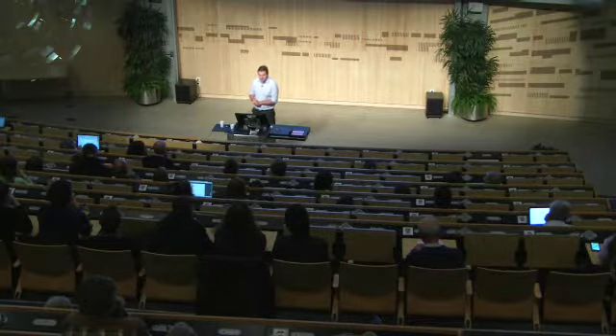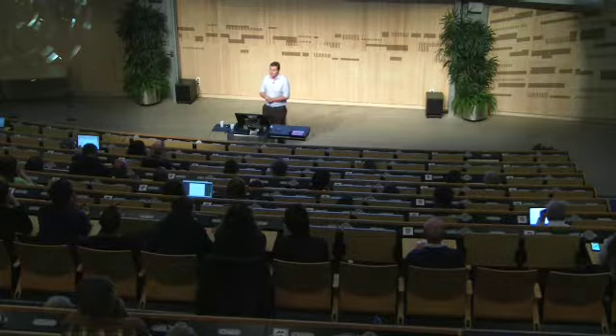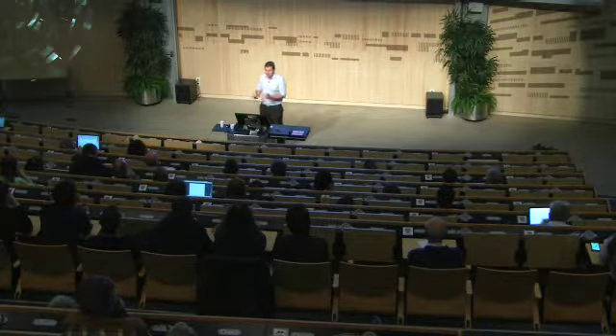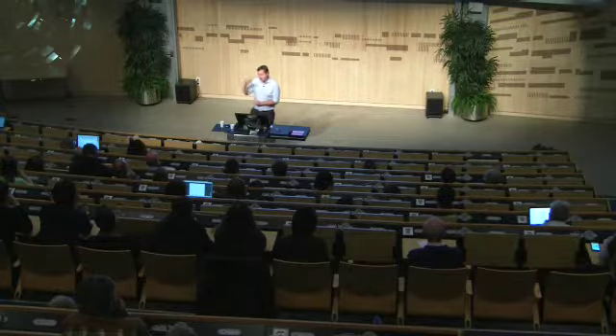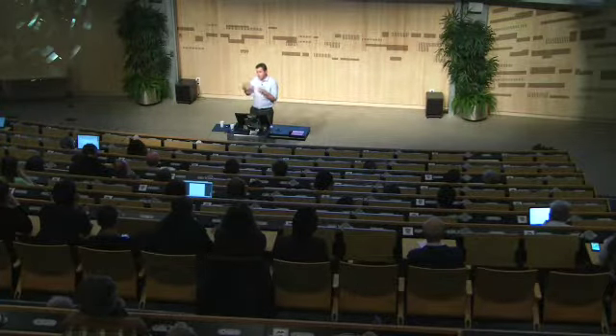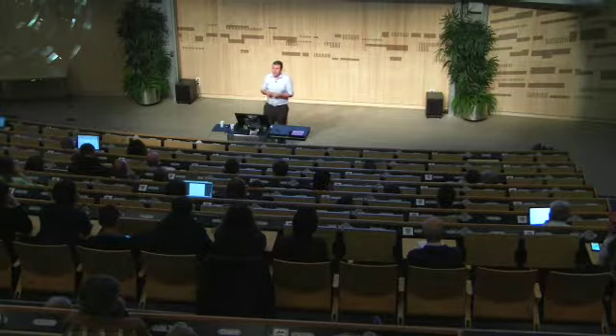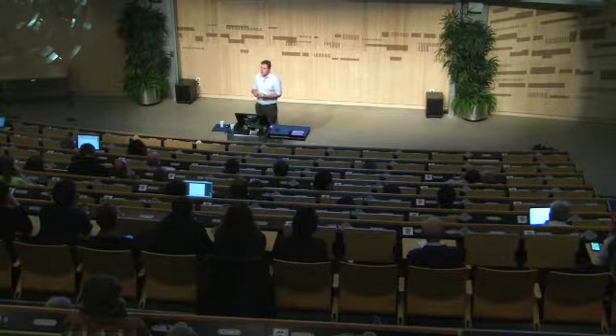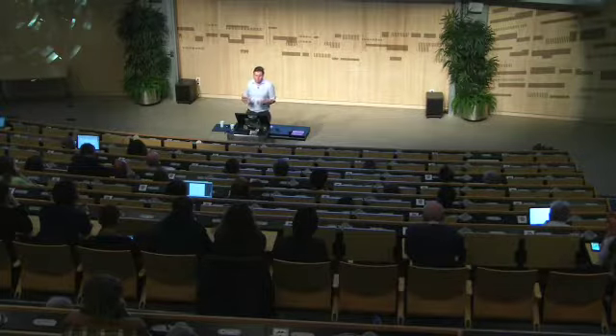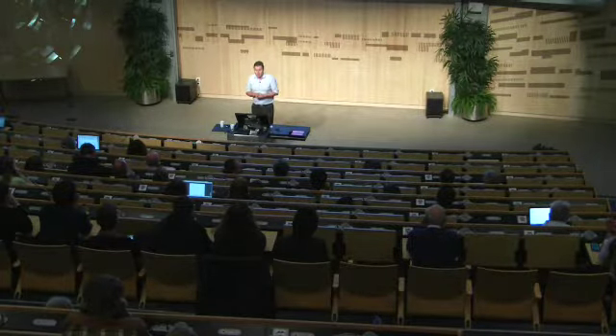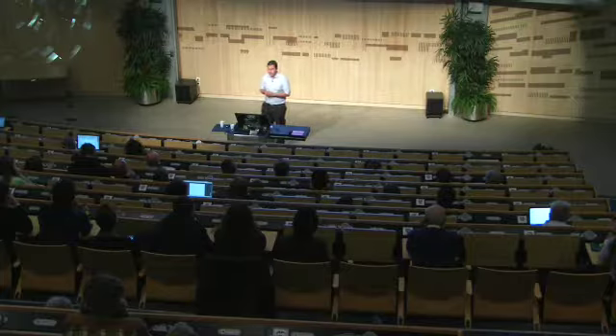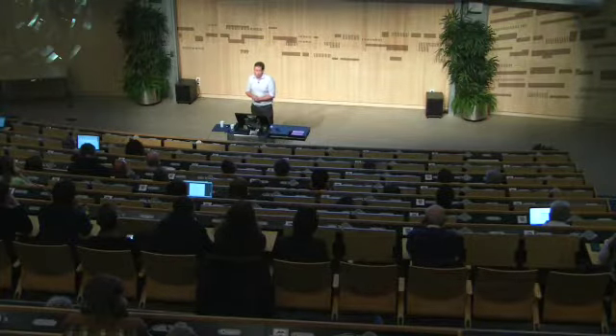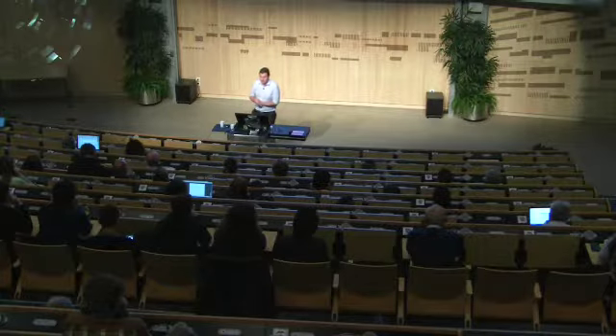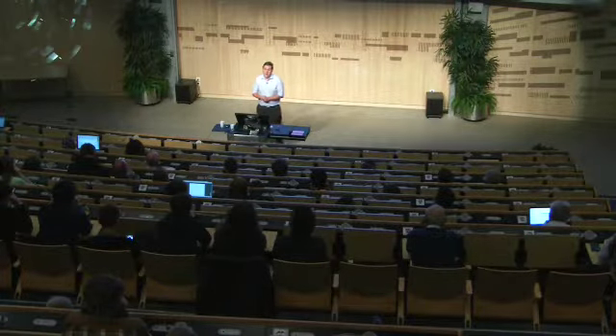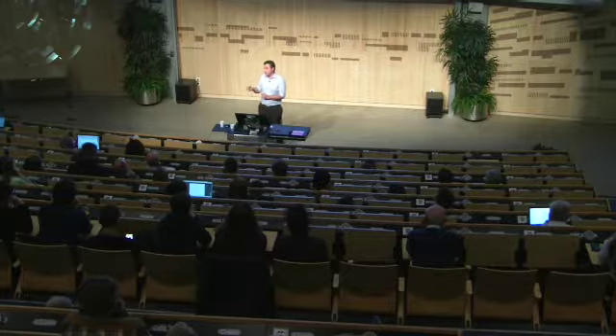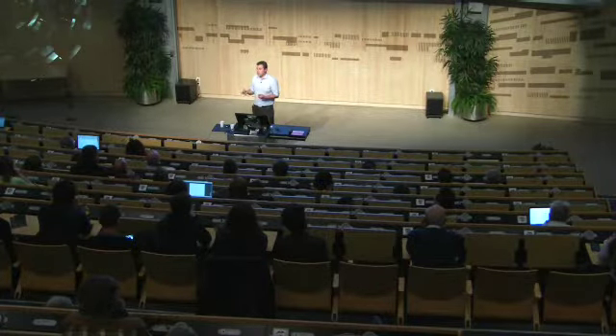This is Medipix 3's charge summing. One of the tricky things about photon counting, which is what we're using, is that when a photon interacts in that sensor layer, it produces a charge cloud, and it's that charge cloud you measure. Now, unfortunately, that charge cloud can be quite big, both through electron drift, the height of the sensor and the bias, but also because you get secondary events. Some of those secondaries can move up to 140 micron, in fact a mean path of about 140 microns in CZT. So that has an intrinsic problem: one incident photon can be seen by 2 pixels.